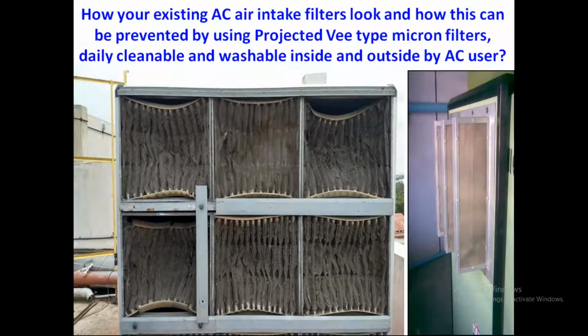You find so much blockage in the HEPA filters. Ultimately, the airflow across the air is being sucked by the fan. The suction pressure, or the vacuum pressure measured by the fan, is only the static pressure in Pascal, and ultimately that will drop. What is there in the atmosphere is not able to be sucked by the fan because the filters are all choked.